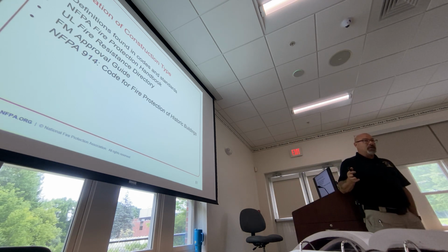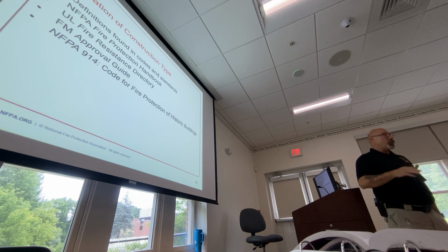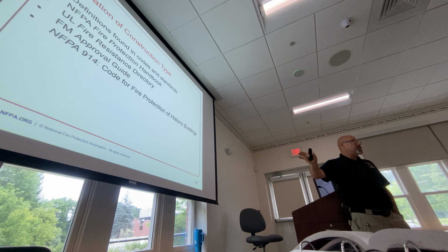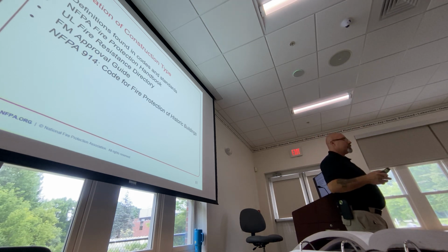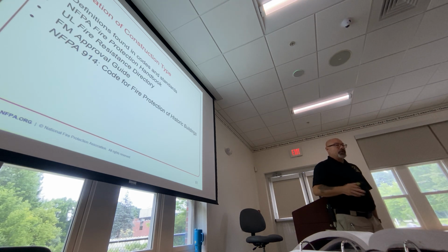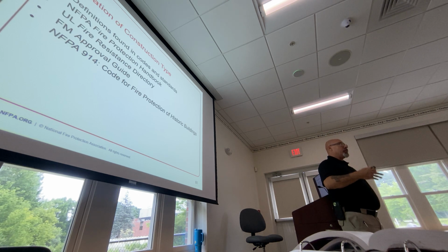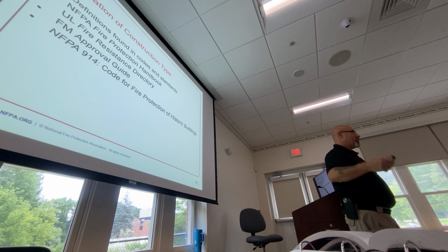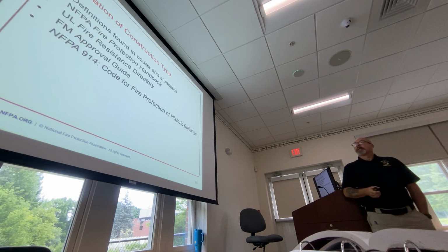We'll talk about different types of construction later, but with the hospital, that actually reclassified the entire hospital as a Type 5, the least restrictive construction type for the entire building. Okay, so it completely threw everything off. That affects their funding. Hospitals get funded based on passing the life safety code. There's a lot of things that could happen there.